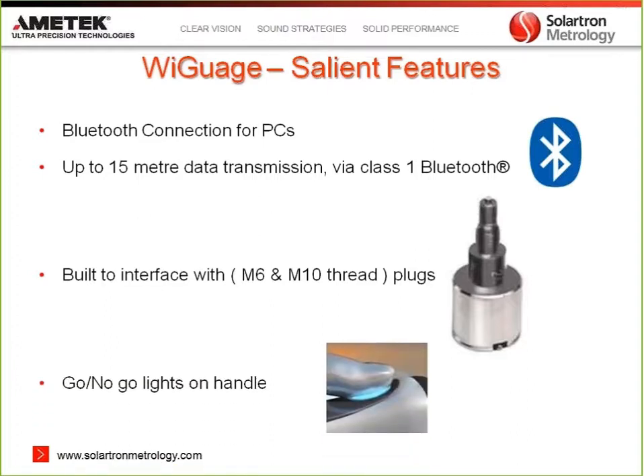The wireless hand tool is simple to use. On the tool itself you have a go/no-go switch which has an LED inside it. Every time you press this switch, a signal is sent to the PC indicating whether the part has passed or failed. It has other uses too - you can program these buttons to reset, preset, or zero readings as well.